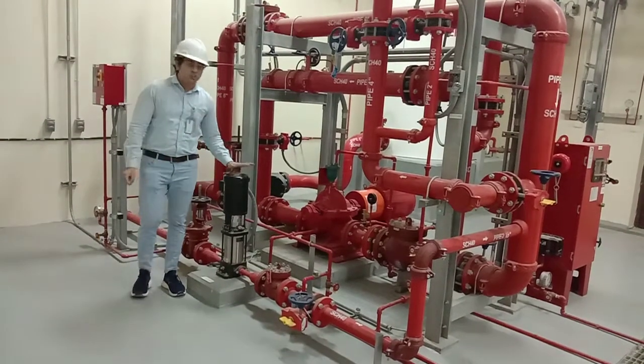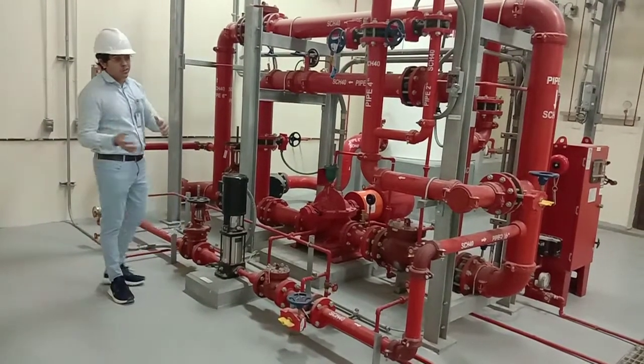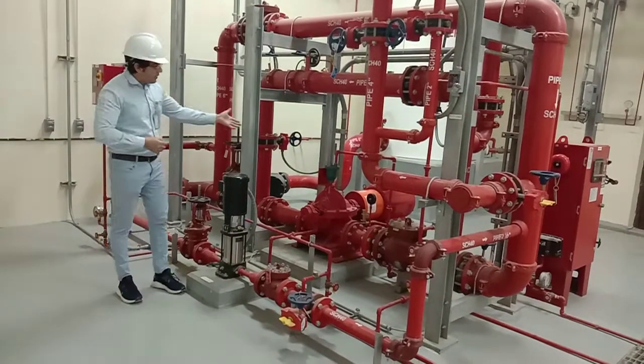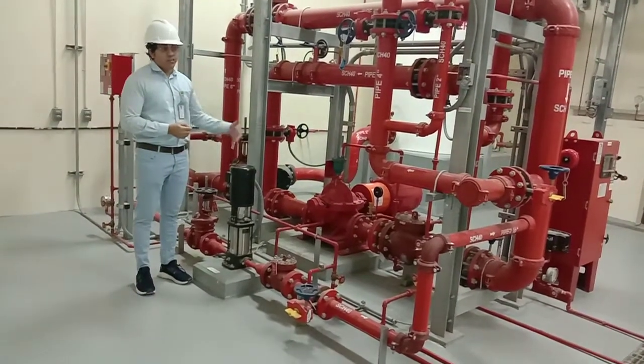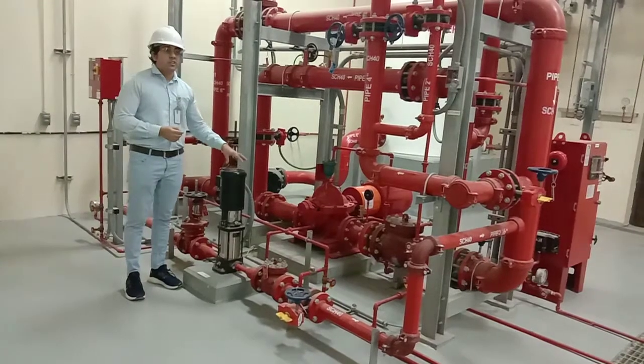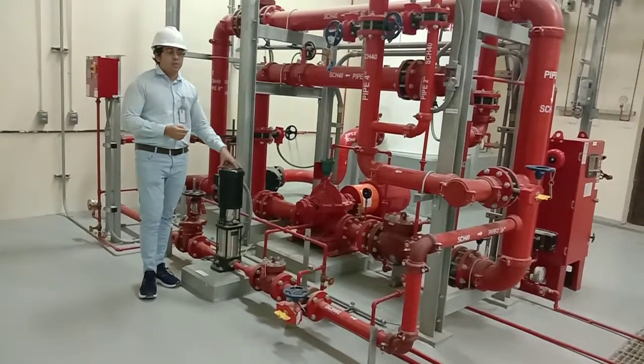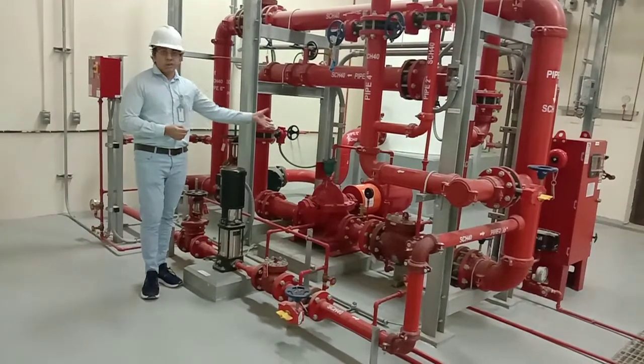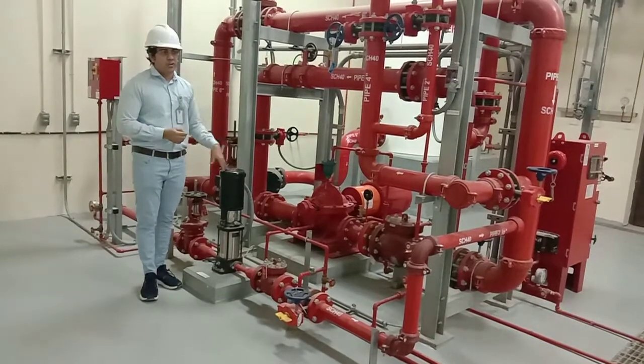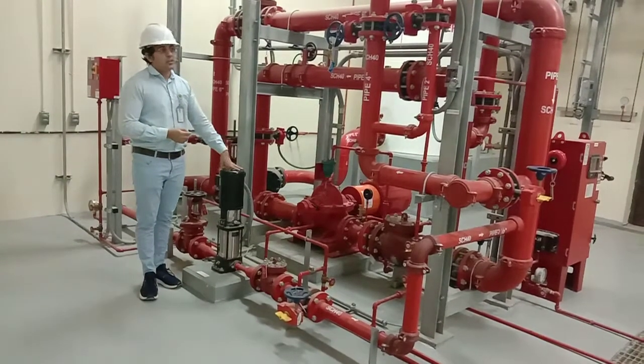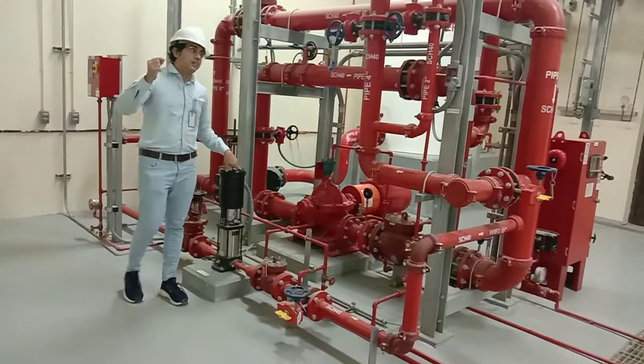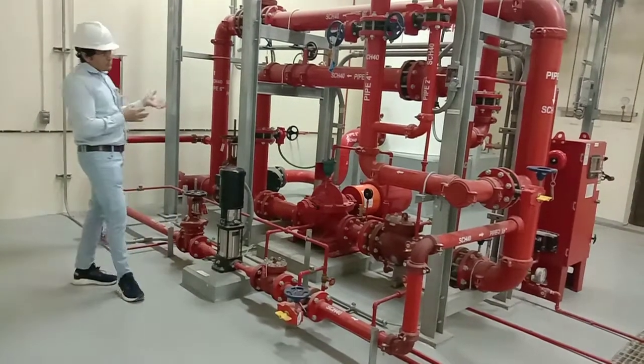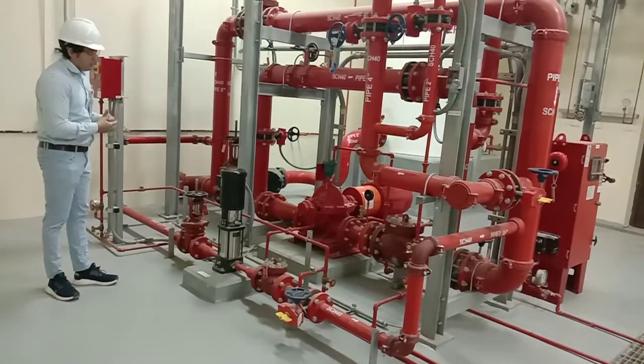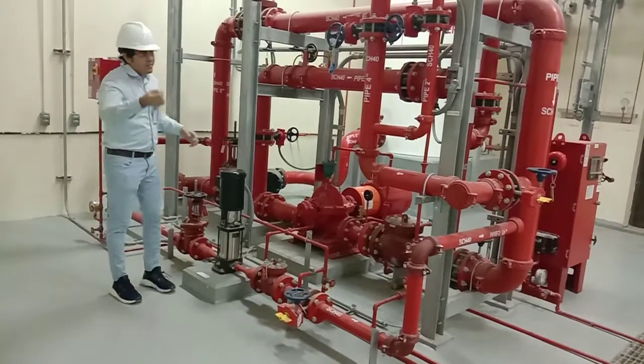Now, what is the size of the jockey pump, right? As we discussed in our class, if the main pump size is, let's say, 500 GPM, the capacity of the jockey pump should be like 5% of the main flow. Sorry, 1% of the main flow. So we have 5 GPM capacity, and the pressure should be 10 psi higher than the rating of the main pump. This is what NFPA says as a rule of thumb. We just want to maintain the pressure, right?